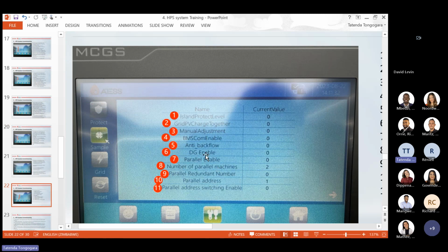And then if you have a generator, DG enable, that's your diesel generator, should be enabled for your SOC max and minimum to take effect. You have to enable this one. For your generator to start automatically, you enable this one. And then in the event that you have a parallel system, you set parallel enable to 1. Number of parallel machines: if you have 2, you set it to 2. If you have 4, you set it to 4.